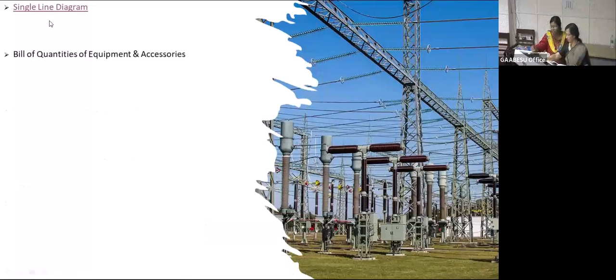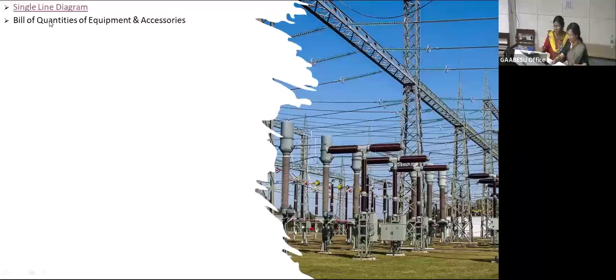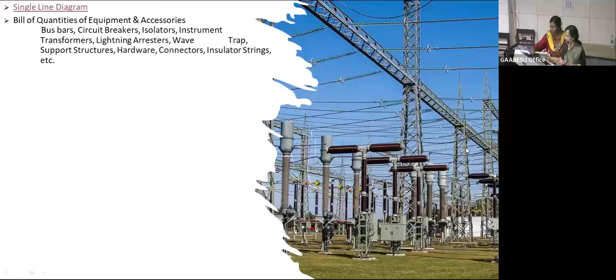So after drawing up a preliminary single line diagram, before going for tendering activities, we prepared the bill of quantities to give the tenderer an idea about the requirements for the substation. The bus bars, circuit breakers, isolators, instrument transformers, lightning arresters, wave trap, support structure, hardware connector, insulator strings, etc.